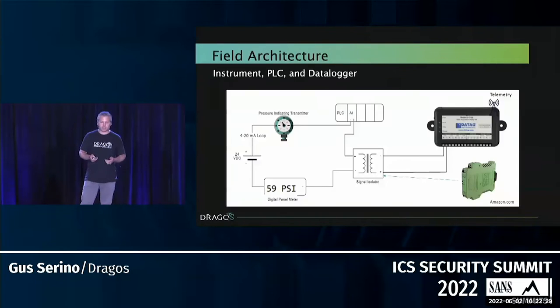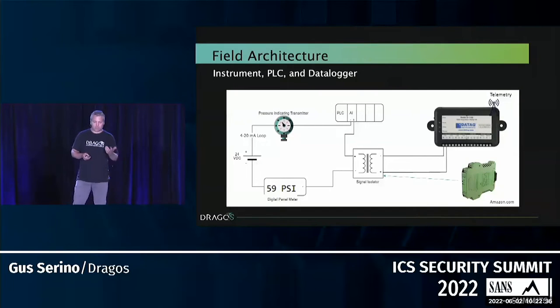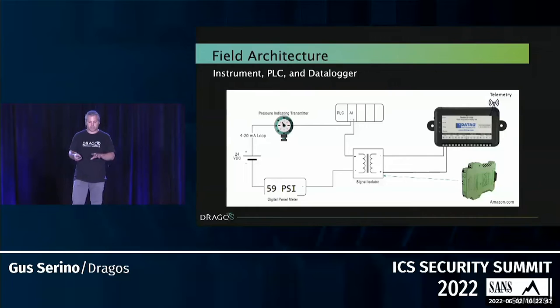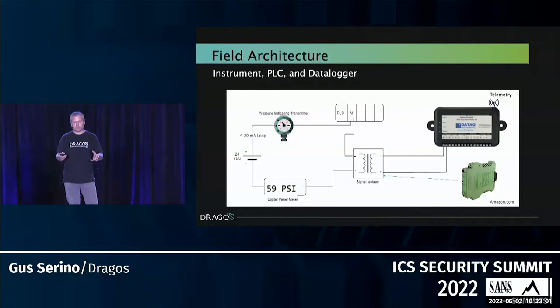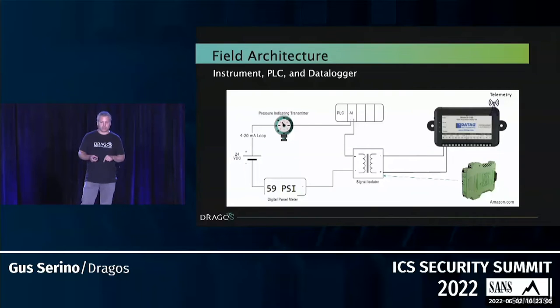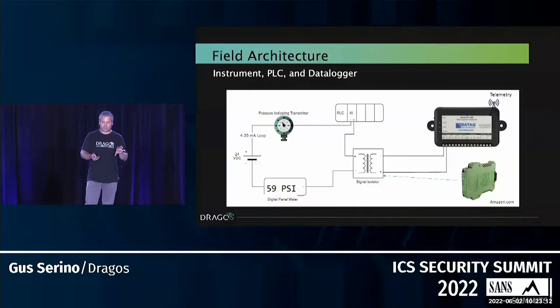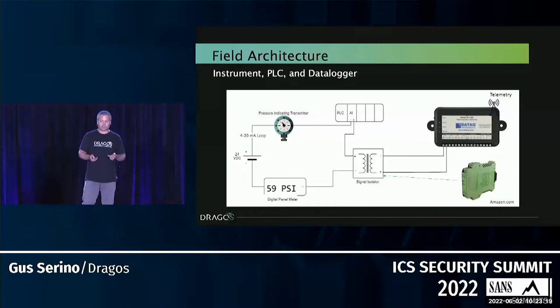We were fortunate we had a lot of this infrastructure already in place. On the field side, the traditional 4–20 mA loop has a 24V DC power supply sending current through the pressure transmitter up to the PLC, through a signal isolator, through a digital panel meter for local indication, and back to the power supply. The signal isolator — that green device on the lower right — takes a copy of the 4–20 mA signal and sends it to the data logger via its own separate telemetry, which could be cellular, plain old telephone line, or whatever is available.